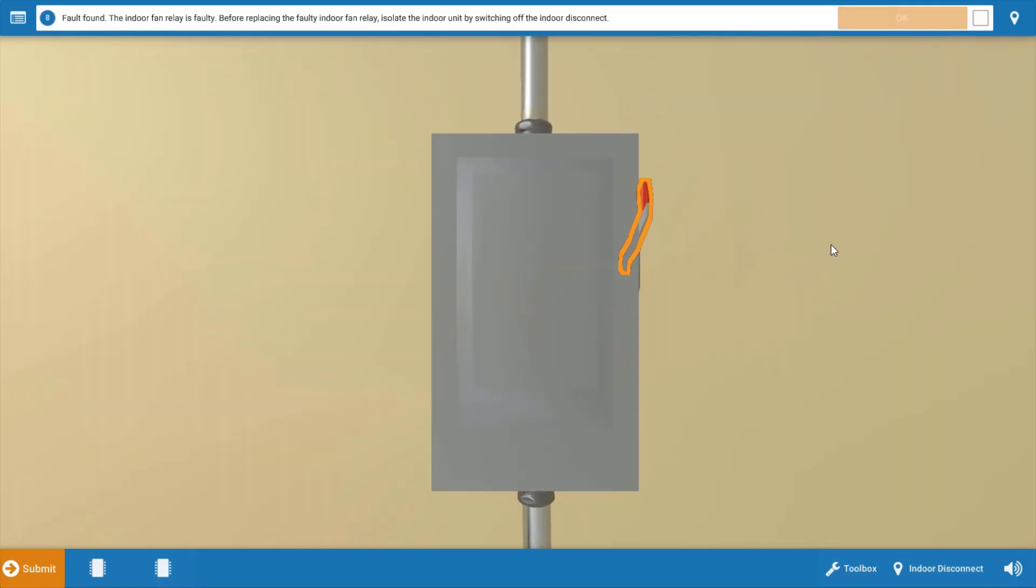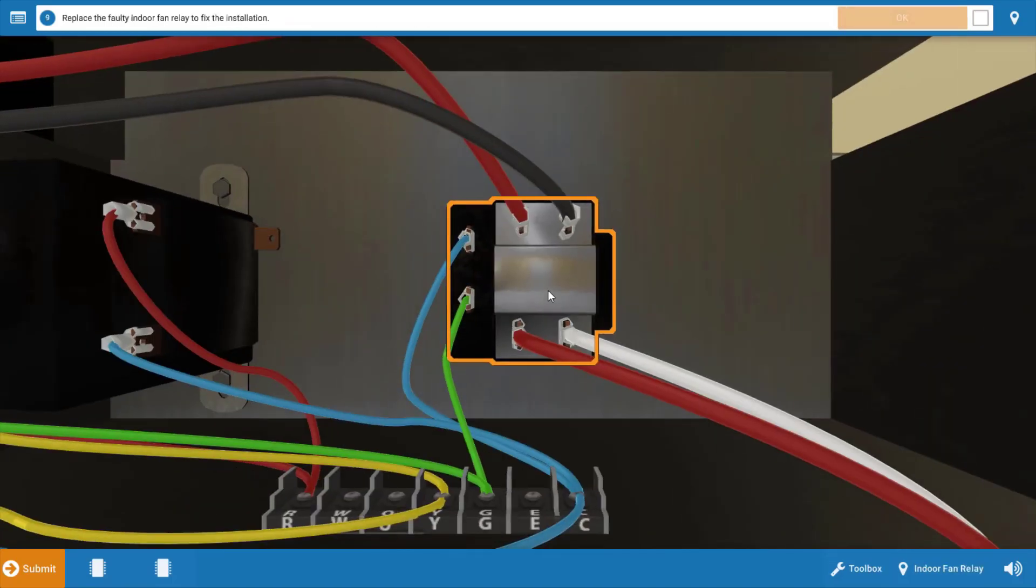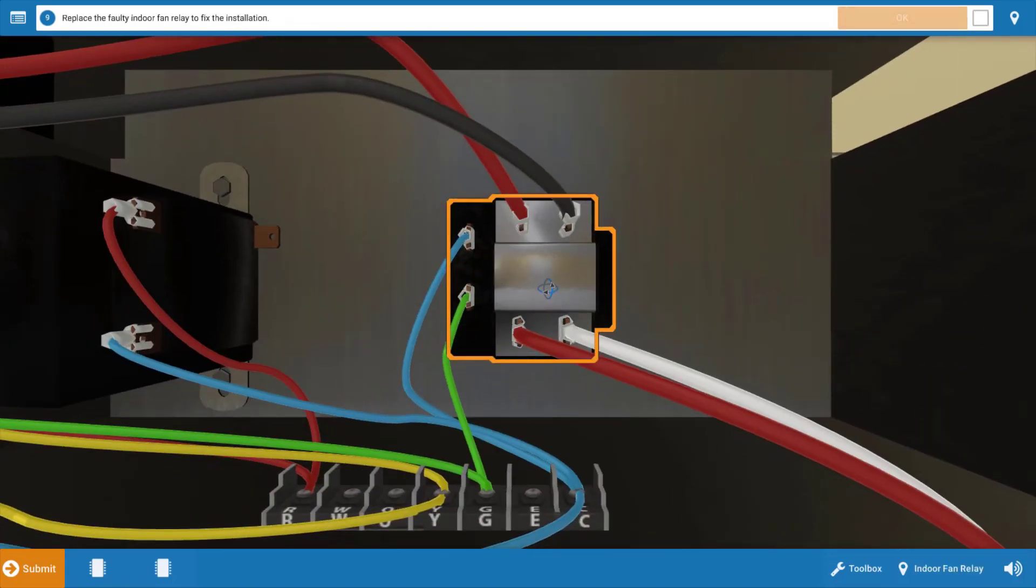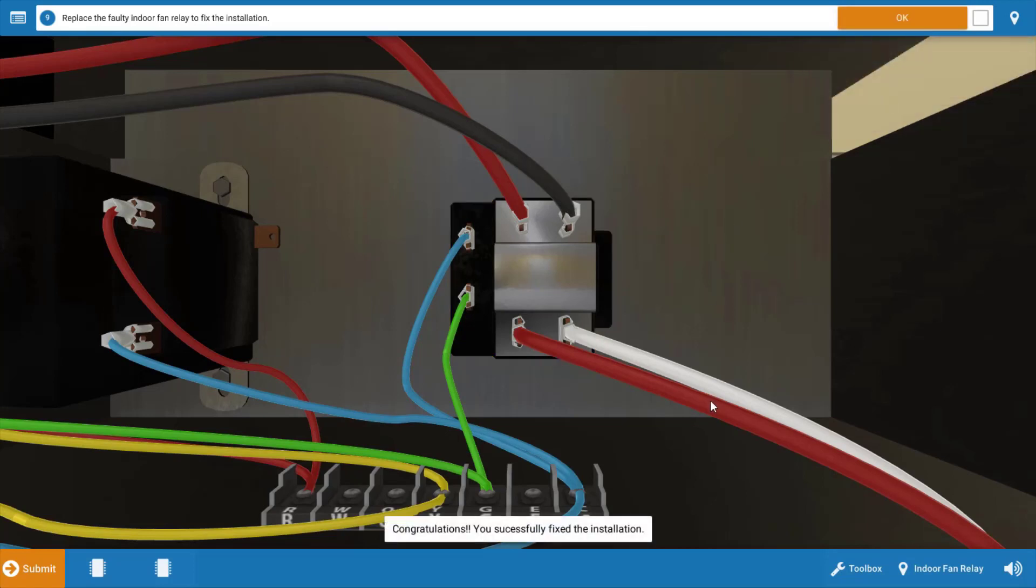Now, if you want to, you can do a resistance check of the coil, but that's really not going to be necessary. We've got 24 volts to it and it's not pulling the contacts in. So our indoor fan relay is the source of the problem here. Turn off your disconnect, click OK on the procedure guide and click on the indoor fan relay to replace it. And when you click on it, just simply click replace on the menu here. And that solves our problem.